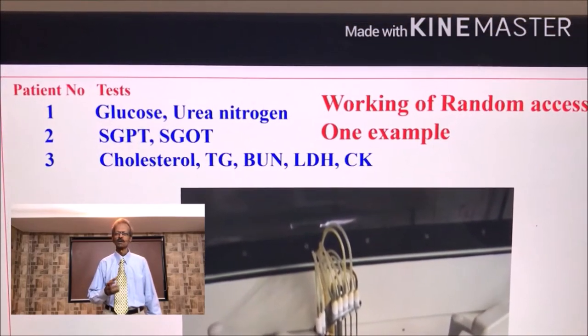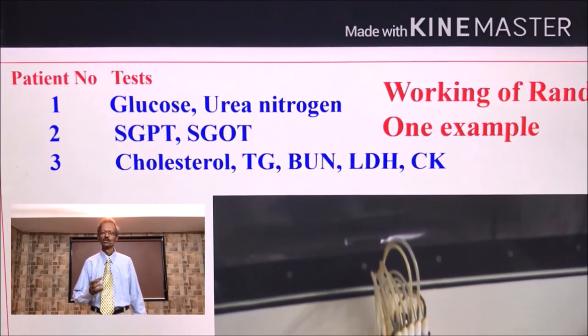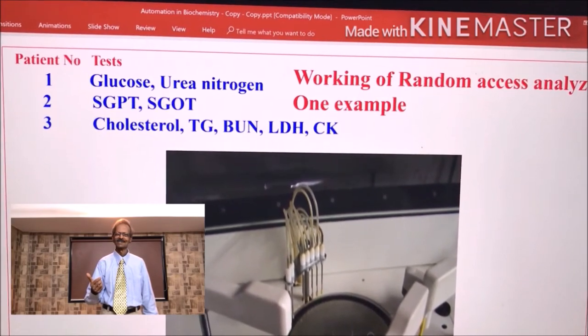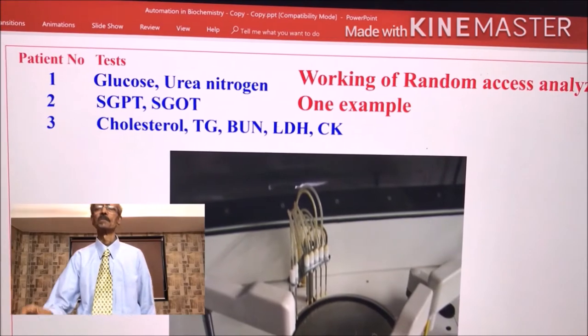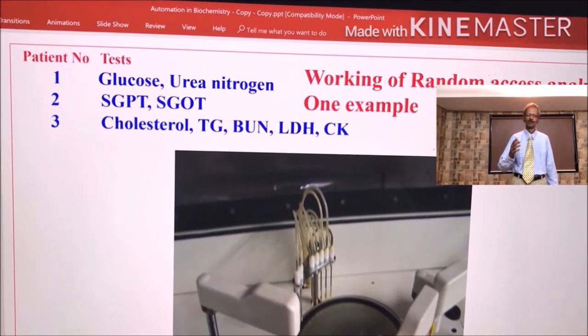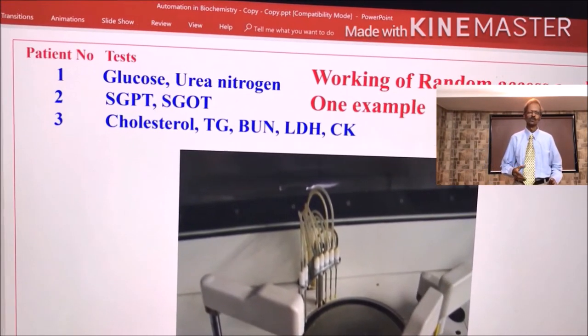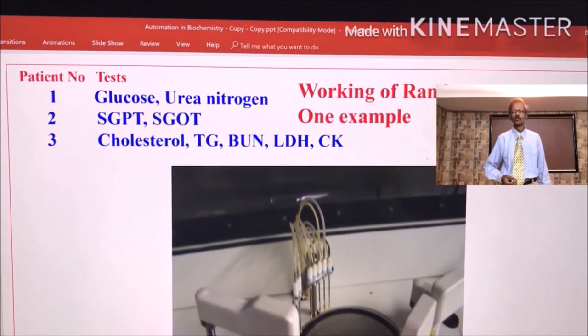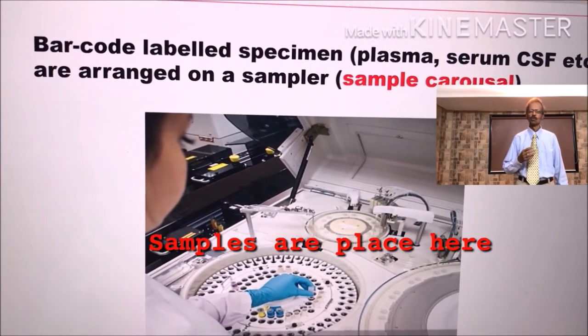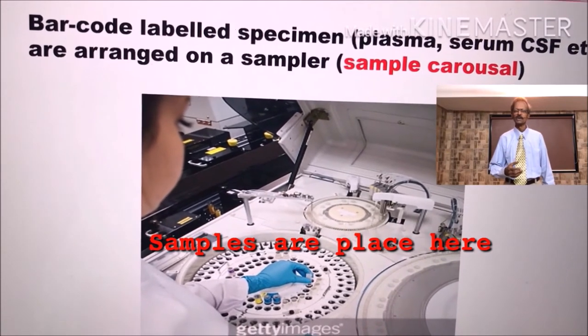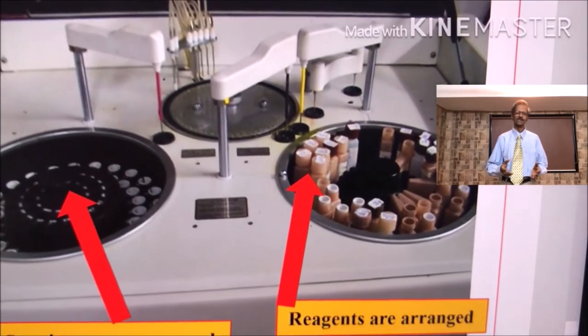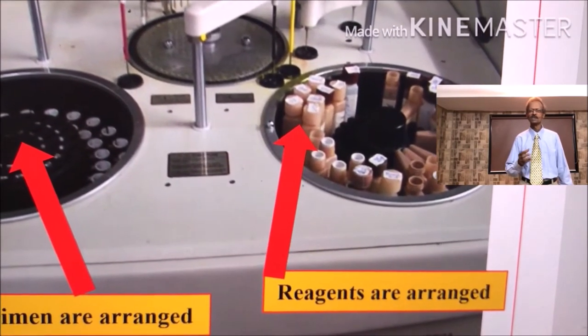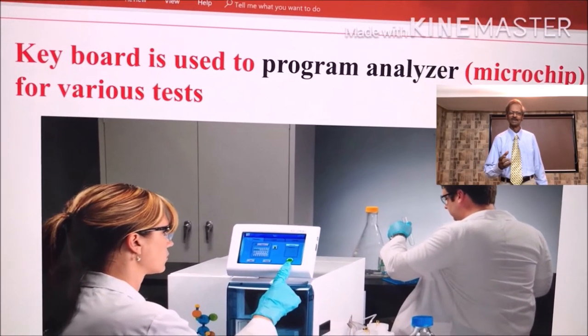Meaning of random access analyzer means this analyzer will finish up all the tests in a random manner. Now let us see how fully automated analyser works. For that matter, we will take an example. Today, for this example, there are three patients. Patient 1 for glucose and urea nitrogen, patient 2 for SGPT and SGOT, and patient 3 for cholesterol, triglycerides, BUN, LDH and CK determinations. Barcode labelled specimens are then arranged on a sampler. Barcoded reagent bottles are arranged on reagent carousel at specific allotted numbers.